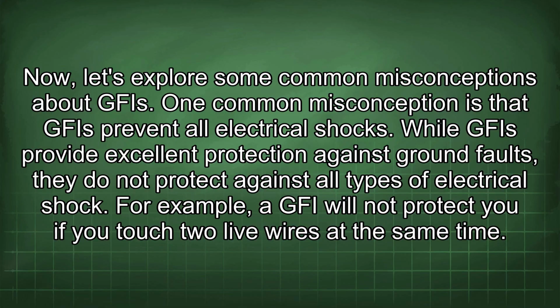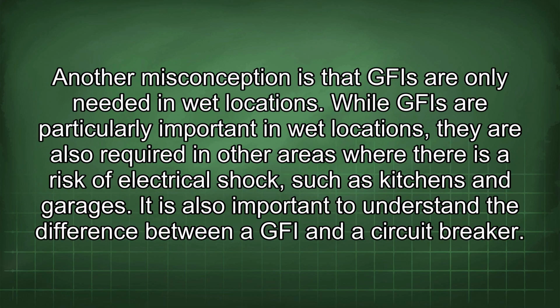One common misconception is that GFI prevent all electrical shocks. While GFI provide excellent protection against ground faults, they do not protect against all types of electrical shock. For example, a GFI will not protect you if you touch two live wires at the same time. Another misconception is that GFI are only needed in wet locations. While GFI are particularly important in wet locations, they are also required in other areas where there is a risk of electrical shock, such as kitchens and garages.